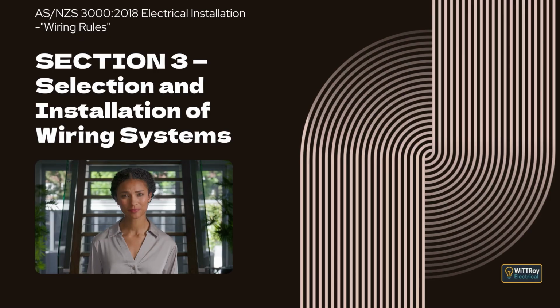Clause 3.11 Underground wiring systems. This clause explains the requirements for wiring systems that are installed below ground. Underground wiring must be suitable for the environment it is placed in, protected against damage that could reasonably occur during excavation or ground movement, and installed in a way that reduces the risk of accidental contact or damage in the future.